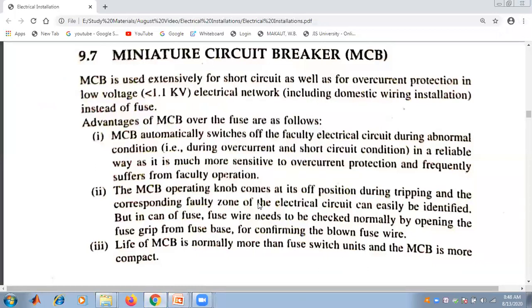First, miniature circuit breaker or MCB is used for short circuit as well as for overcurrent protection in low voltage electrical networks, that is voltage below 1.1 kV. The electrical network includes domestic wiring installation and MCB is used instead of a fuse.